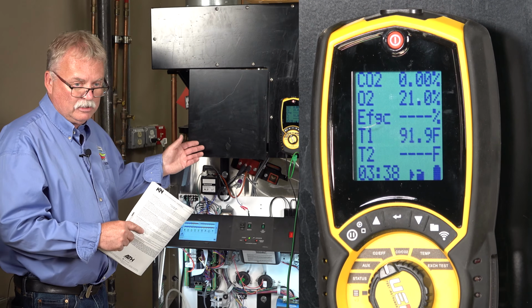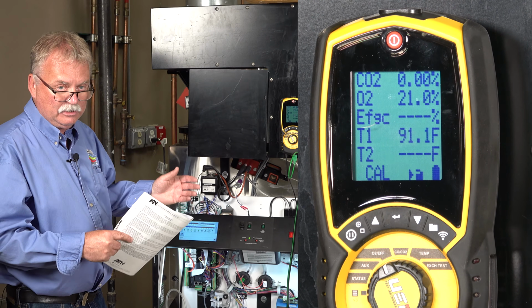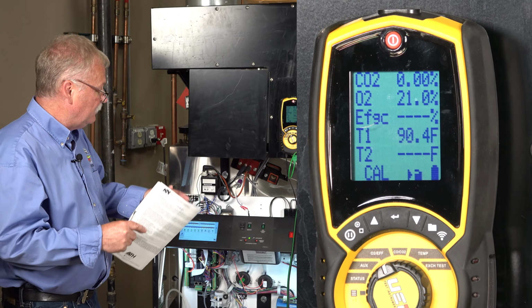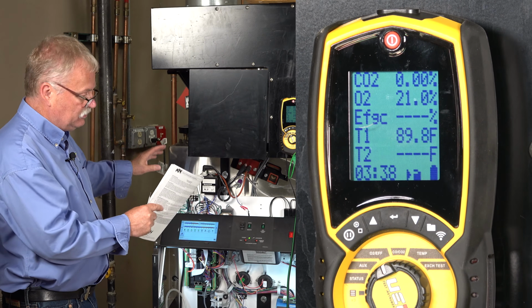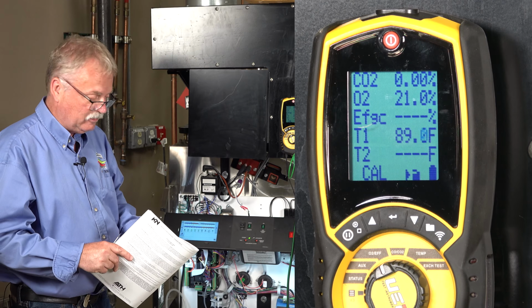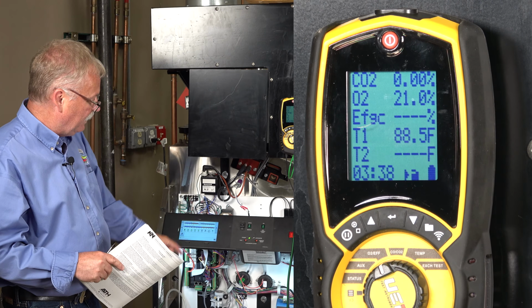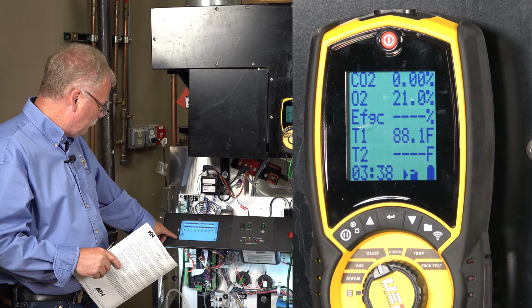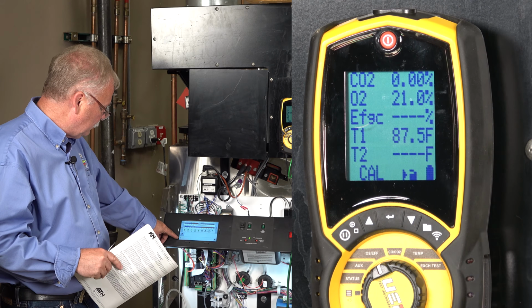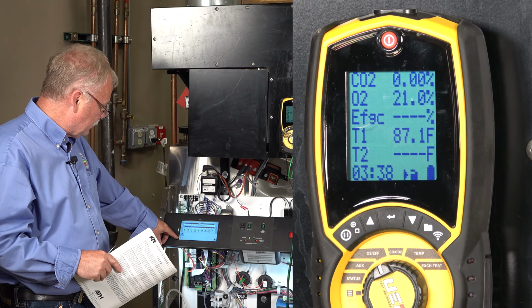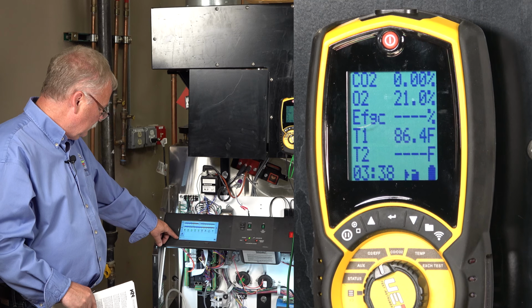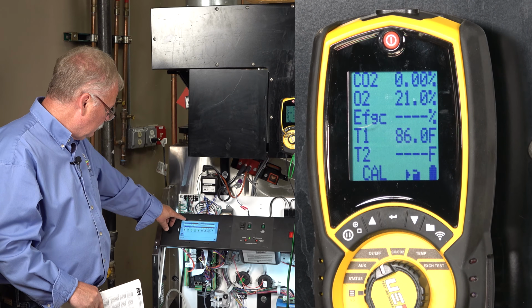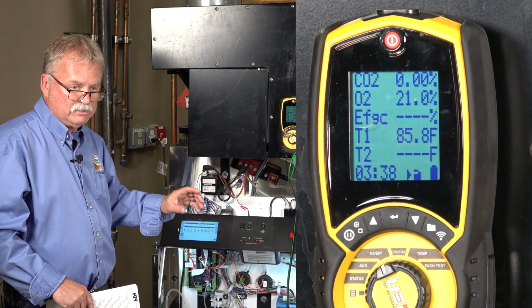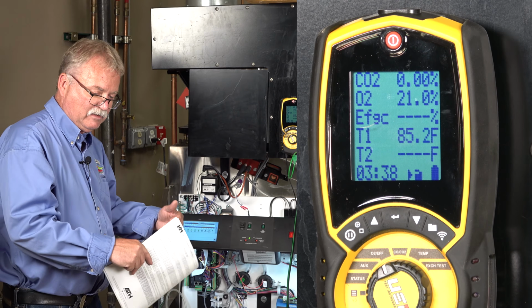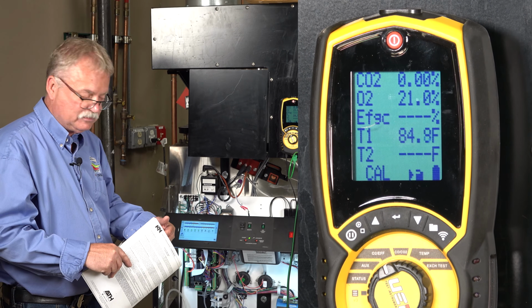That's typical pre-purge. Every high efficiency boiler has a pre-purge. What that does is make sure that whole combustion chamber has no gas in it, just air. That was the pilot valve opening. So right now my pilot is going for ignition. It's in local set point, is what it's called. It's lit. This boiler lights off at 40%. So that means it lights off at about 250,000 BTUs.